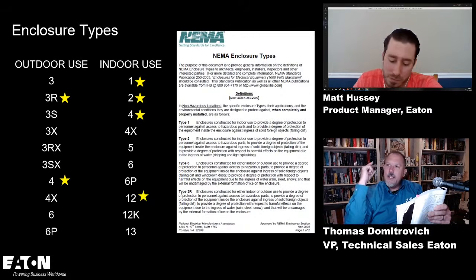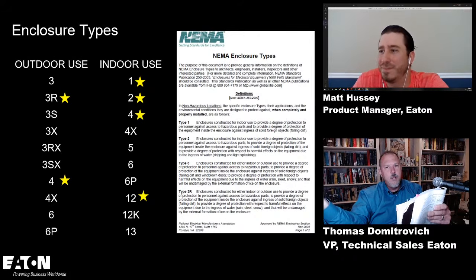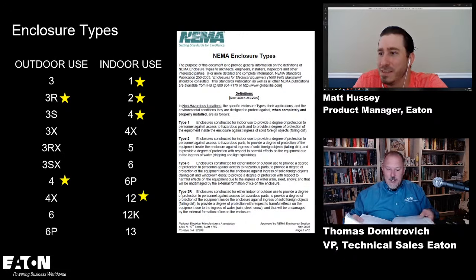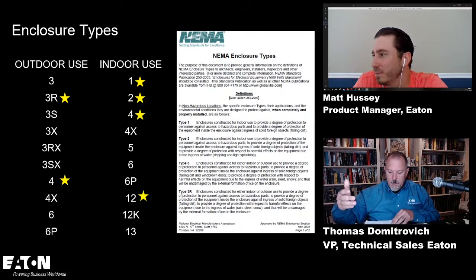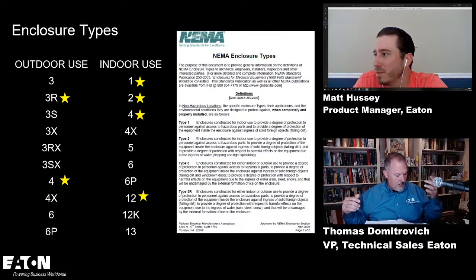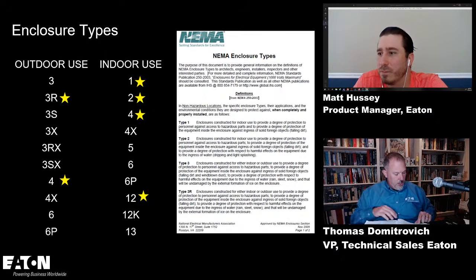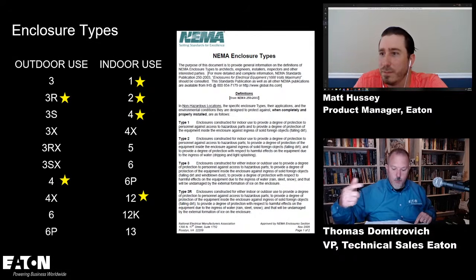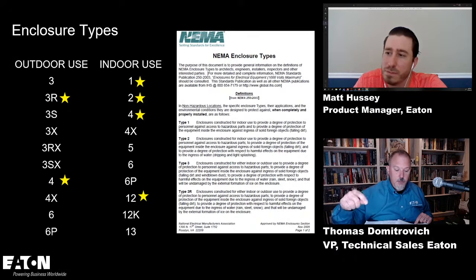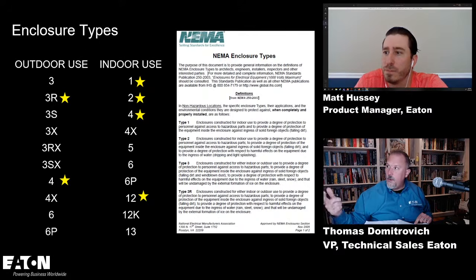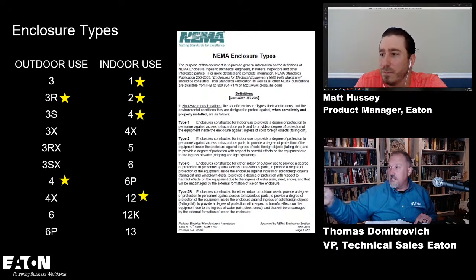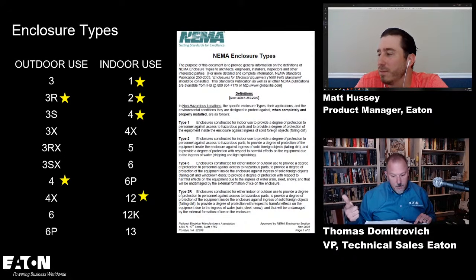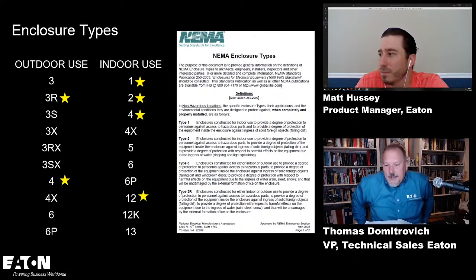Yep. And I made the comment, well, wait a second, I can't use a 3R indoors. And when I look at the NEC in 110.28, now help me, Ryan and crew, but it says enclosure selection. 110.28 says enclosures other than surrounding fence, of switchboard, switchgear, everything, terminations, fire pumps, rated not over 1,000 volts, and locations shall be marked with an enclosure type number shown in table 110.28, and it shall be used for selecting these enclosures for use in specific locations other than hazardous locations. So can I put a 3R indoors? The NEMA document, and it's right there on the screen, says 3R is enclosures constructed for either indoor or outdoor use. But the table does not list a 3R for indoor use. That's my question. I'd love to hear some feedback on that one.